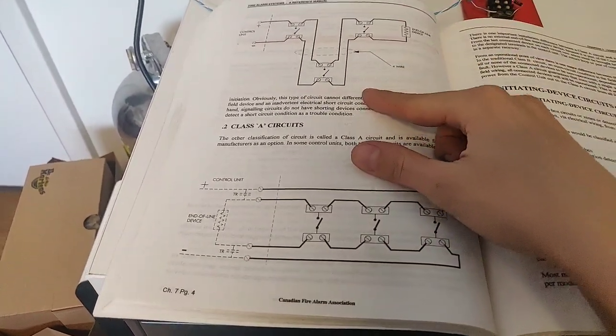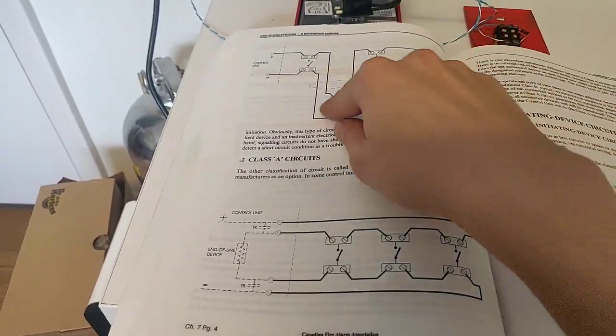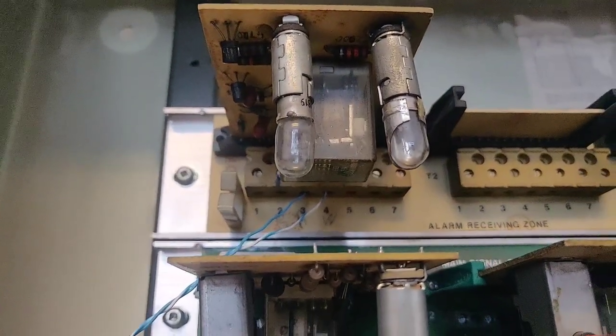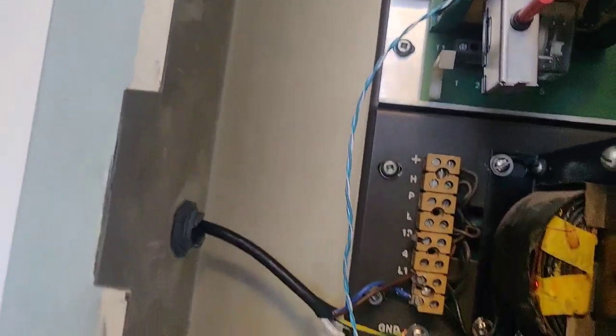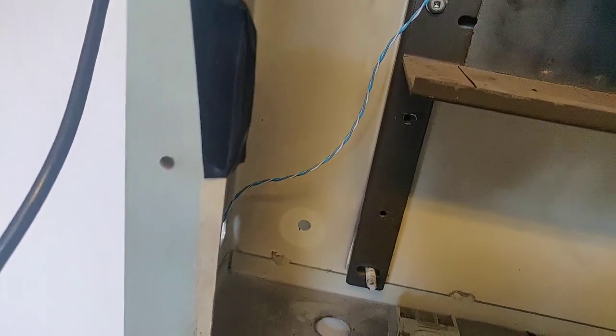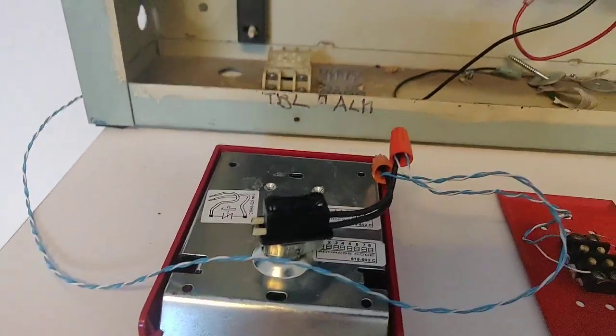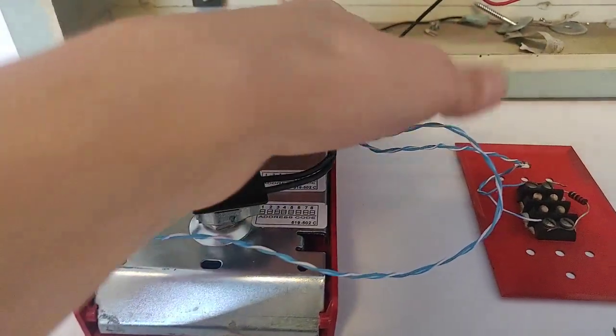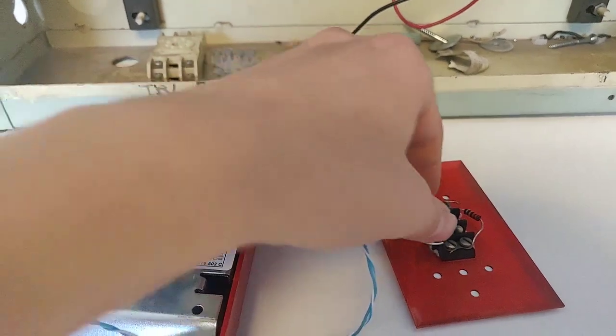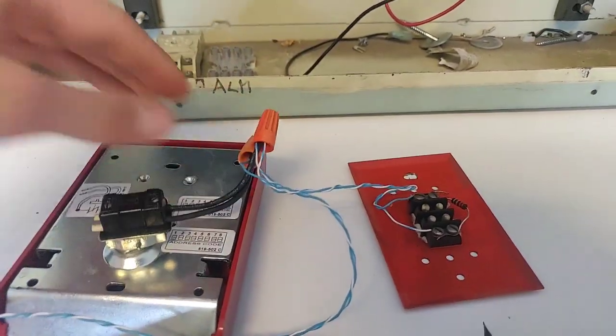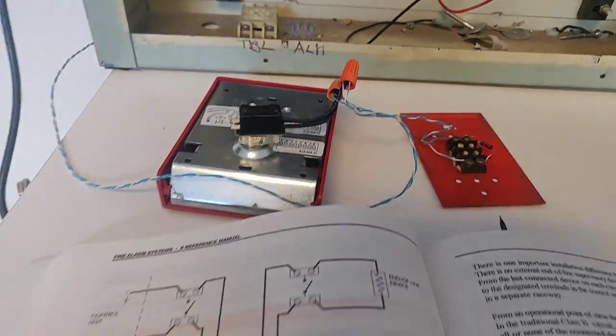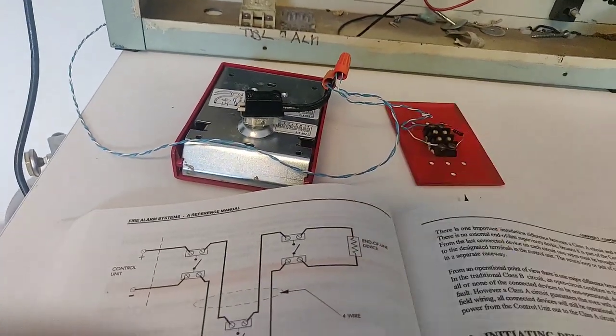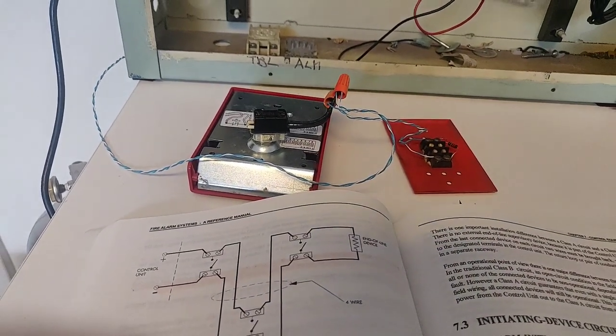The first setup that we're going to do here is this class B setup. So I've got it wired here. So from our terminals three and four, we have the wire. The reason for using the ethernet cable is that it's a lot easier to see on camera, especially when I'm going to have a bunch of wires in this panel. And it comes down here and it goes across to our pull station—you can have as many as you want. But you can see it's just wired to either side of the pull station and then it continues on to our end of line resistor at the very end. So you would have a bunch of devices in between here in a real system. So that's exactly what we have going on here. So let's power on the fire alarm panel and see if this works.